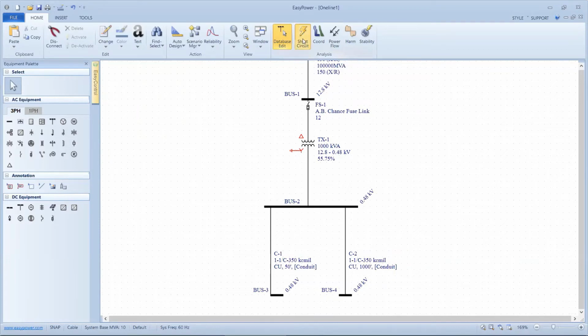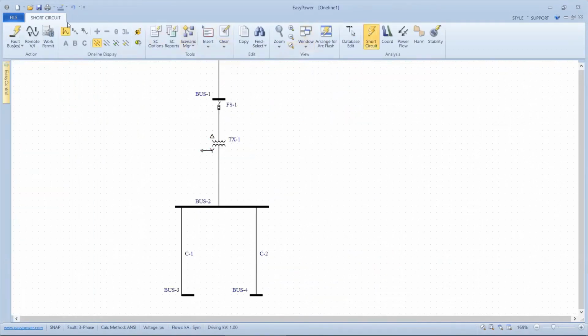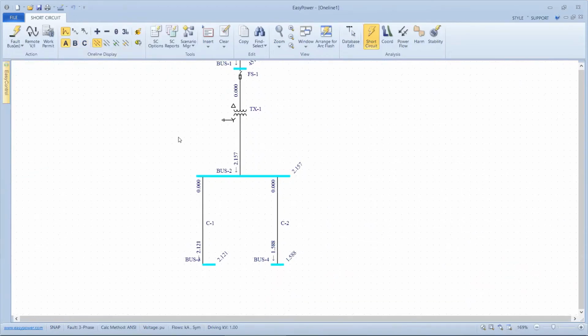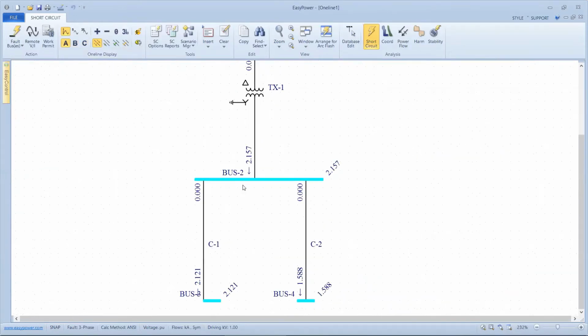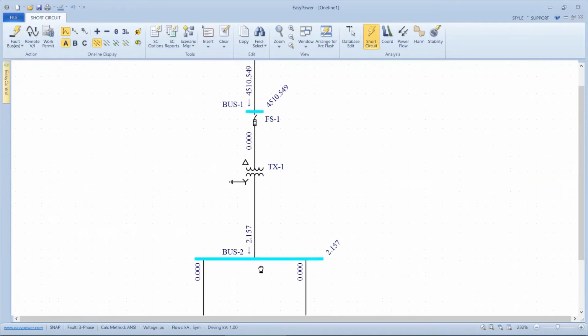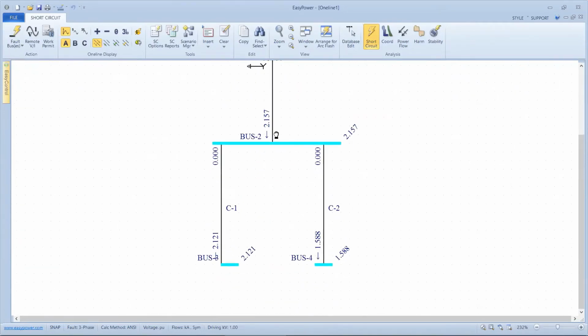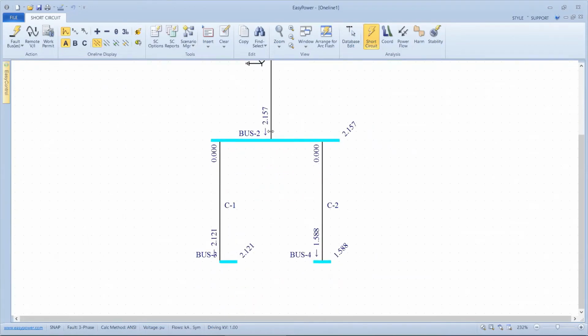So now he's ready to go to short circuit focus. We're on the top row. Look at the half cycle, 3-phase bolted fault, and fault all the buses. And what we're looking at is just the A phase. We can look at all 3 phases, but because we defined it as a bolted fault, they're all the same. He said, Jim, this makes sense. Well, it doesn't make sense, but we'll deal with it.